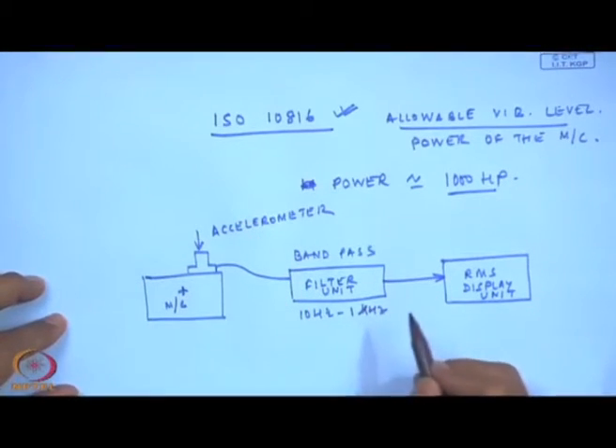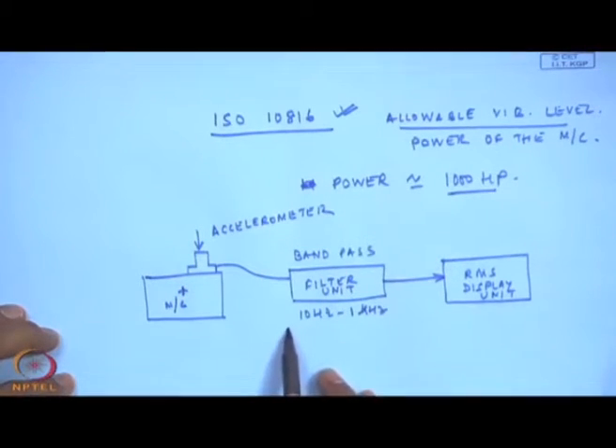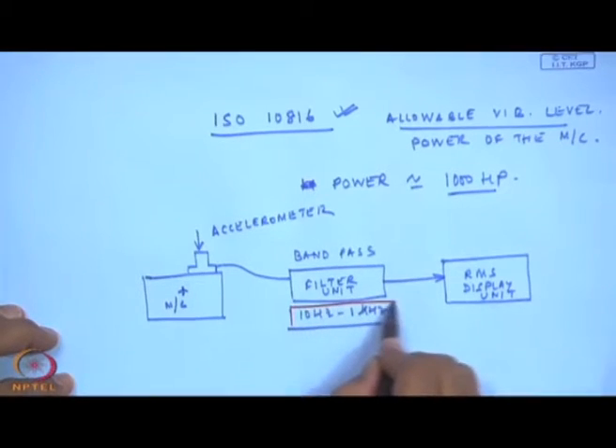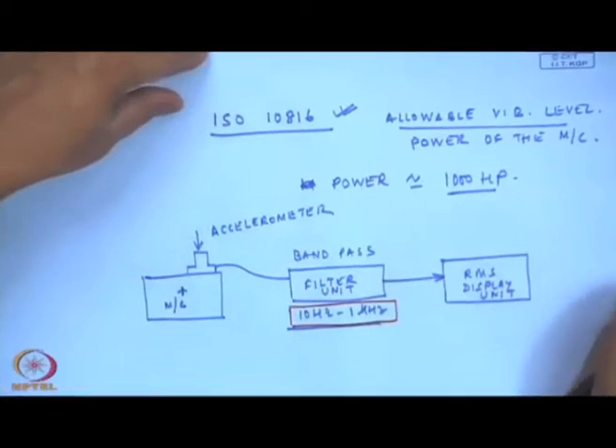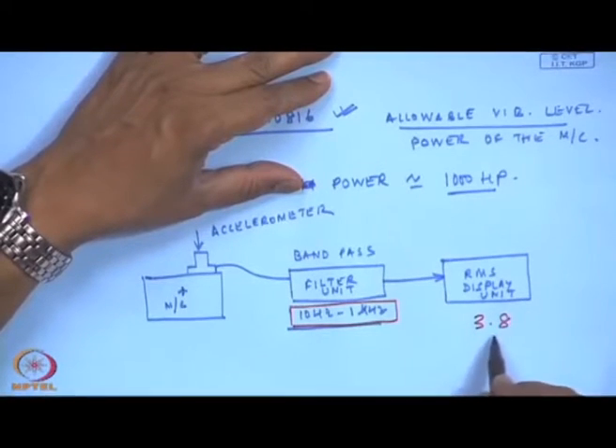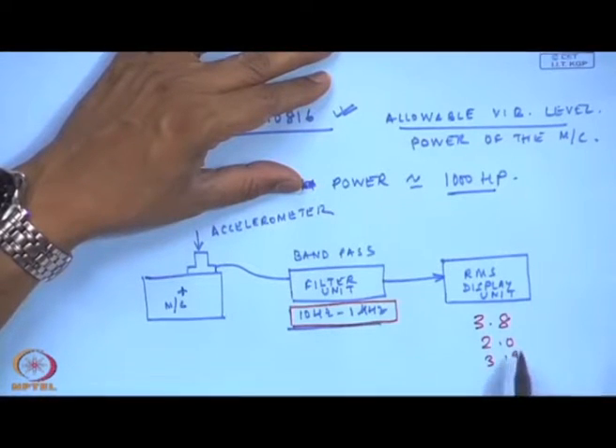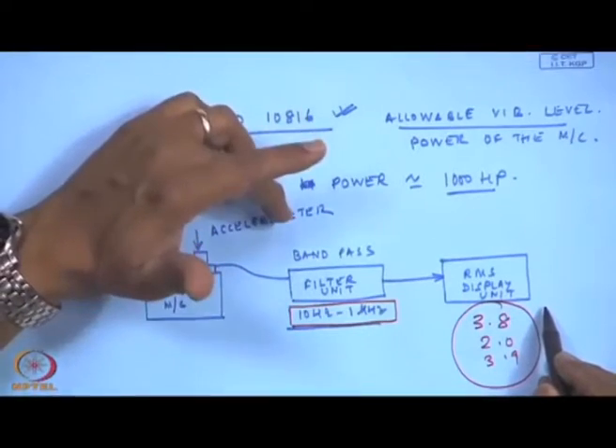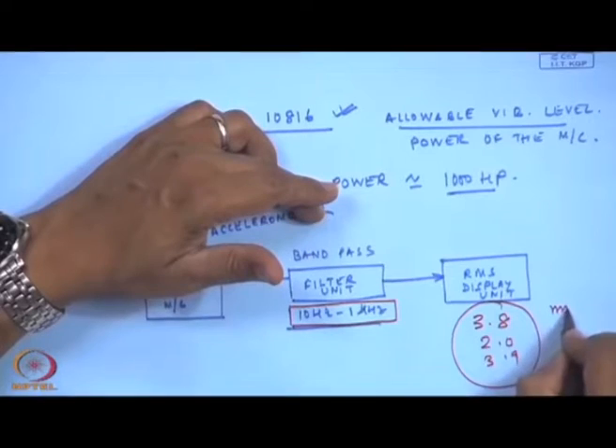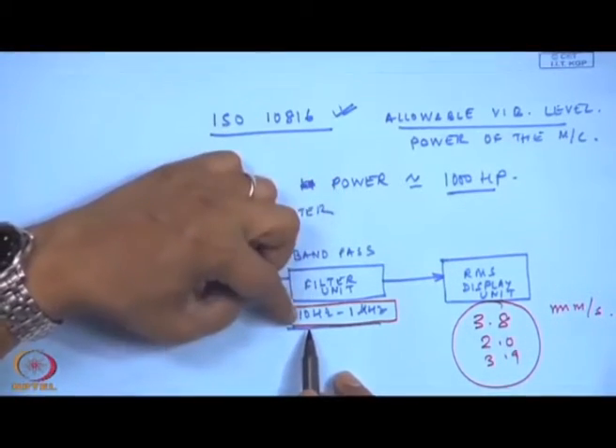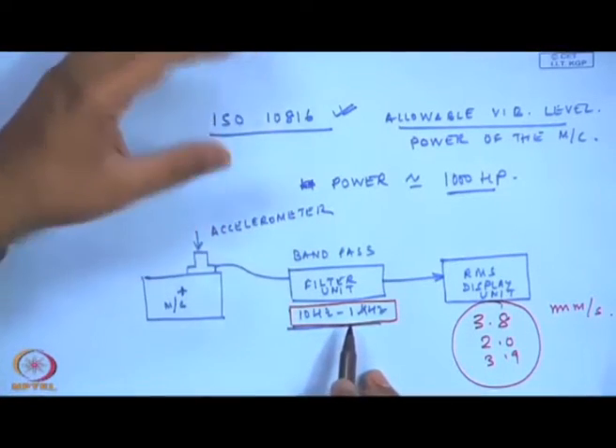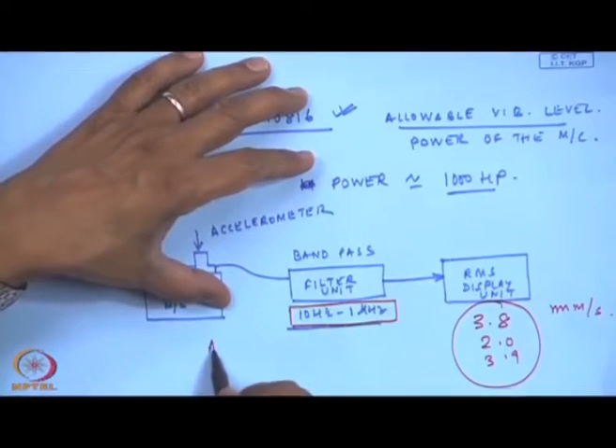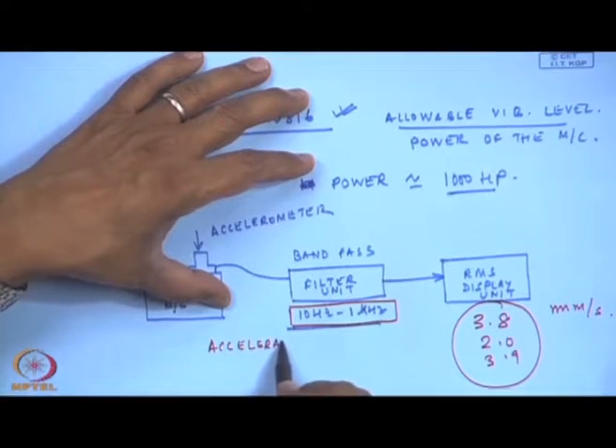One has to keep in mind that the ISO 10816 standard says this is a very important value — it is not just any value. Many times when you go to industry to do troubleshooting of machines, engineers will give you numbers without assuming that everybody knows that this is in millimeters per second, without making sure whether filters were on or off, or even knowing whether it was in acceleration mode, velocity mode, or displacement mode. These kinds of problems do creep in.